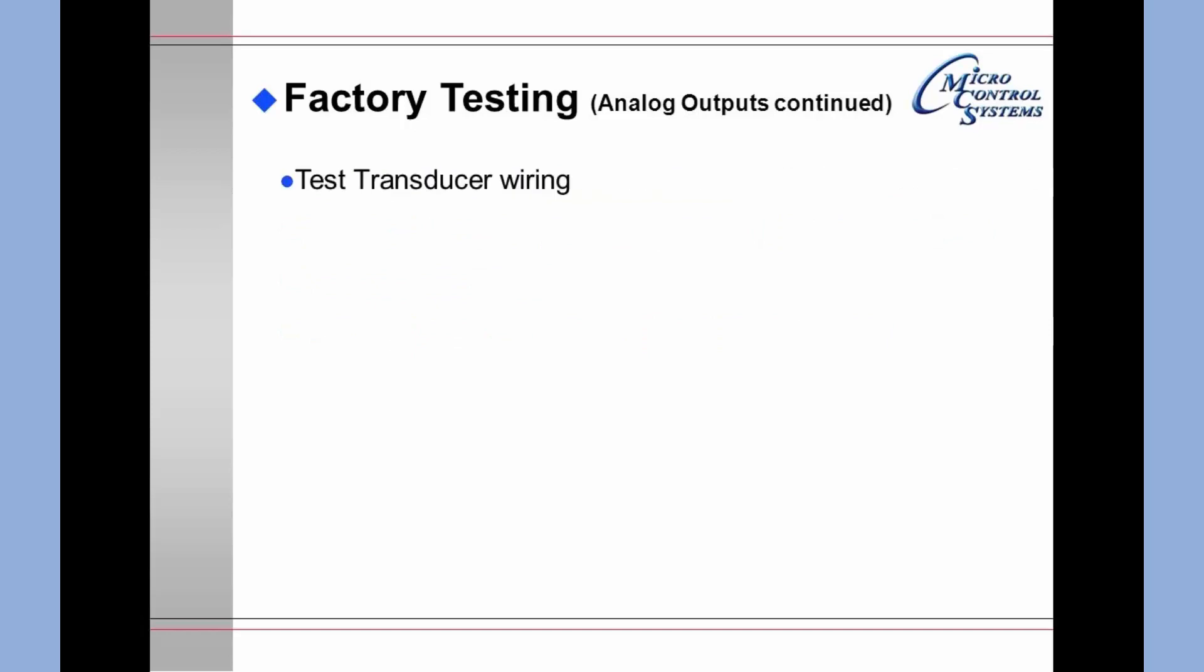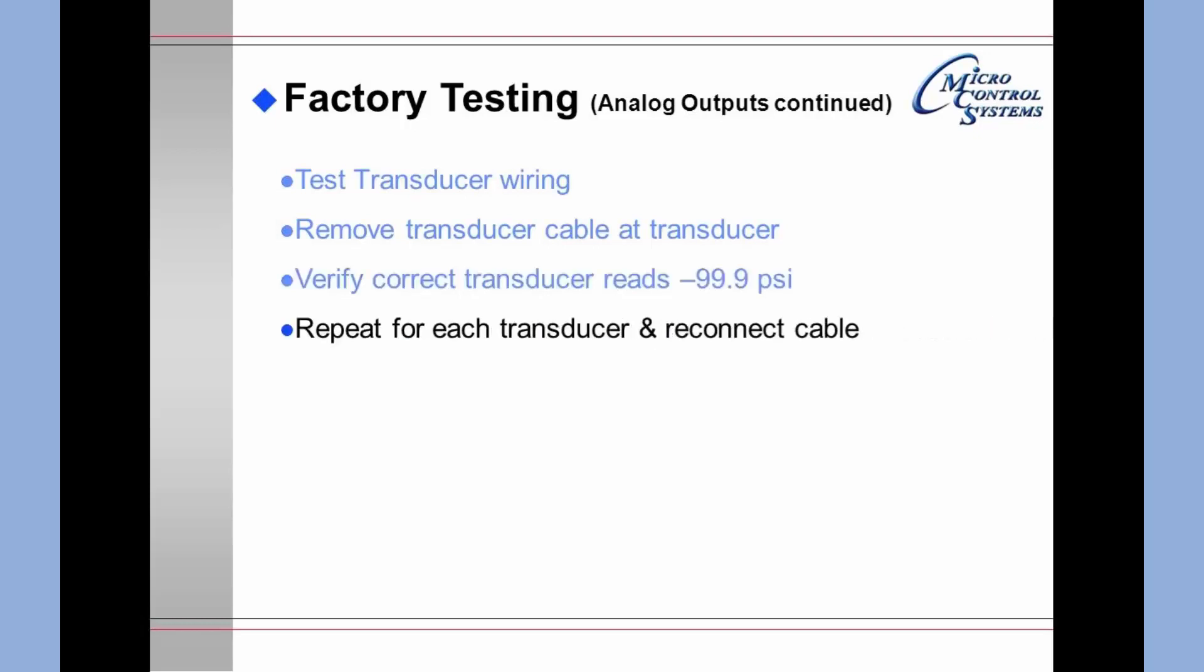To test the transducer wiring, you will remove the transducer cable at the transducer and then verify that the transducer cable you have removed reads minus 99.9. Repeat this for each transducer and then reconnect the cable. Verify that all transducers are reading correctly.